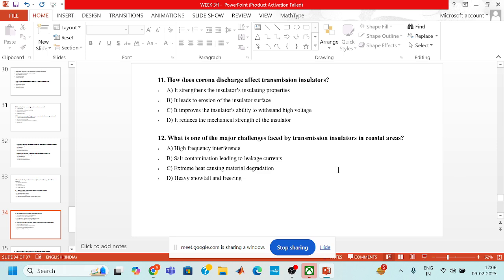So 12th question is, what is one of the major challenges faced by transmission insulators in coastal areas? Option A, high frequency interference. B, salt contamination leading to leakage currents. C, extreme heat causing material degradation. And D is heavy snowfall and freezing. B. Salt contamination leading to leakage current. Yes, mainly in coastal areas, the major challenge faced by transmission insulators is salt contamination leading to leakage currents.